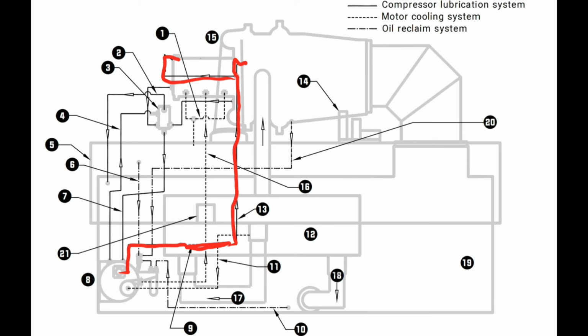Now, that oil heater only runs when the machine is off, and it's trying to maintain that oil between 140 and 160 when the machine is off. Now, once we get the machine online, we want that sump to be able to maintain around 120 to 140 degrees is pretty typical. You just don't want to go below that 120 mark.